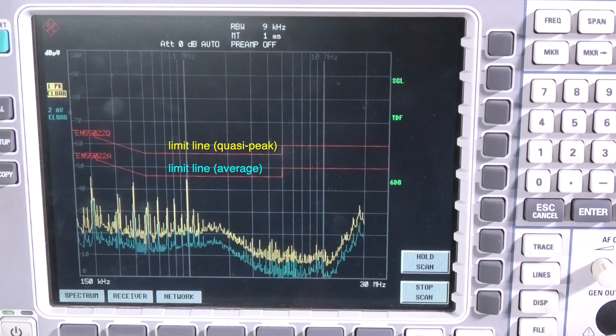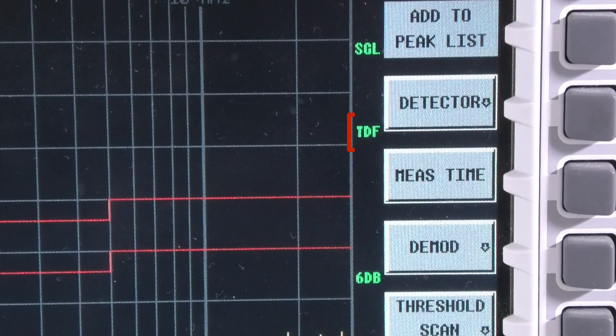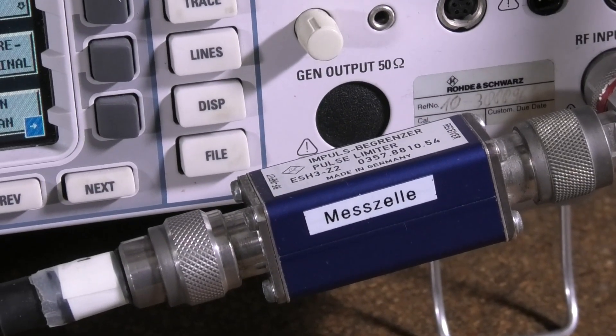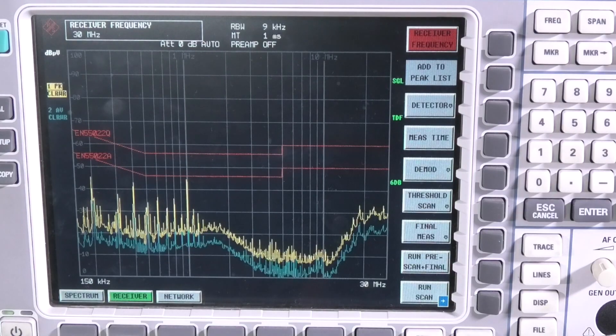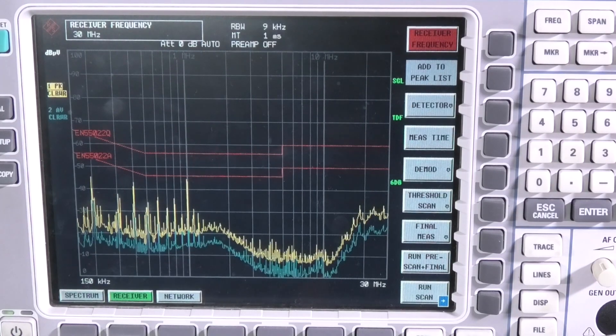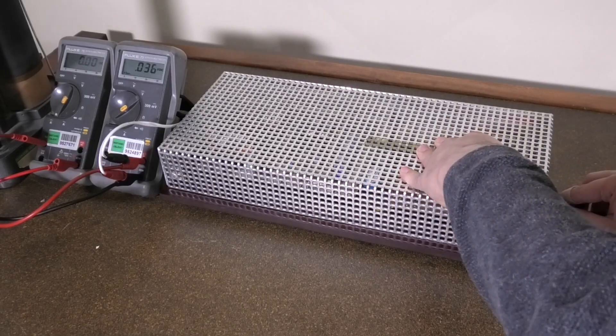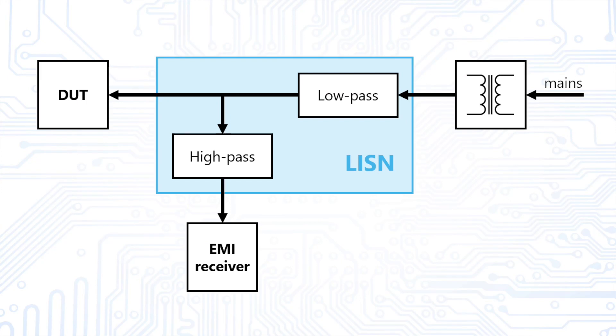By the way, all the terms you see here will be clarified in future videos. For example, a transducer factor TDF has been set here. This corrects the result, as the connected pulse limiter attenuates the measured signal by 10 decibels. Without the pulse limiter, our receiver could take serious damage when we turn on our DUT because of rapid current transients. Keep in mind that the measurement shown covers only one aspect of EMC measurements: conducted emissions.